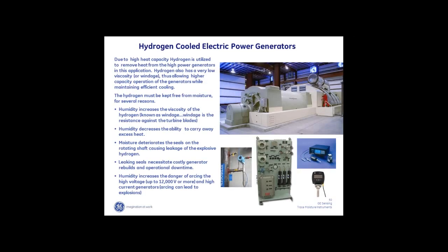Another application we run across is in power plants: hydrogen-cooled electric generators. Hydrogen is used to take heat away from the generator. It is the most thermally conductive gas and the lightest gas, so it produces less resistance against spinning the turbine. We have to dry that hydrogen out completely — they're looking for parts per million levels or below. It's a very popular application for us because we also measure hydrogen in these applications.